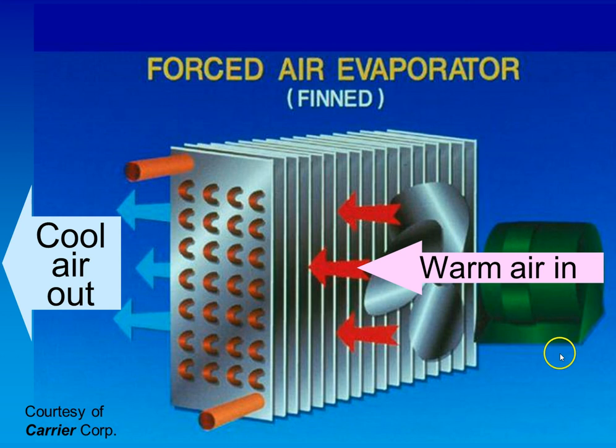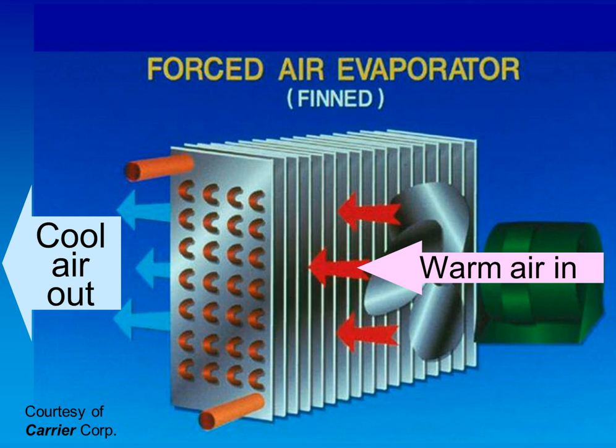One thing I want to make note of is that the freezer and cooler coils differ considerably in construction as far as the spacing between the fins goes. The cooler and freezer coils have larger gaps between the fins than a residential air conditioning system does. It's because these coils operate at temperatures below freezing, and they start to frost up — and if the fins are really close together, they'll ice up rather quickly.